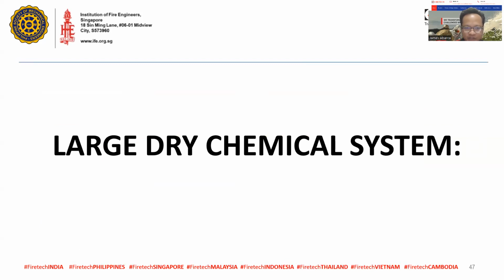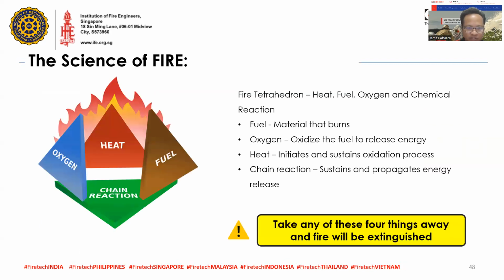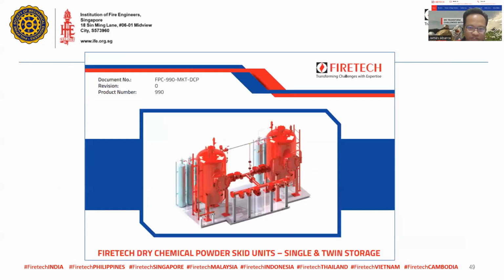Last system that we do also manufacture is what we call the large dry chemical system. It is a fast knockdown system. If you're dealing with water mist, it's a matter of few minutes that will suppress fire. So that's why when we do design, we always consider minutes. In a foam suppression, it's the same matter of minutes as well. But in a dry chemical system, it's a matter of seconds, 3 to 5 seconds. So we are removing the oxygen.